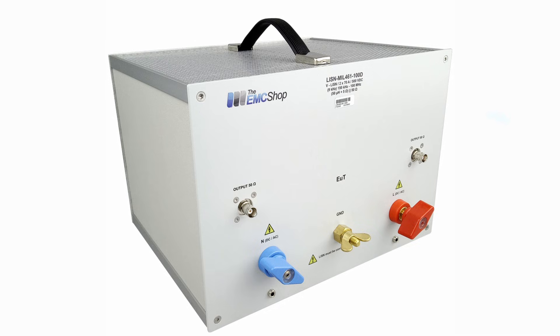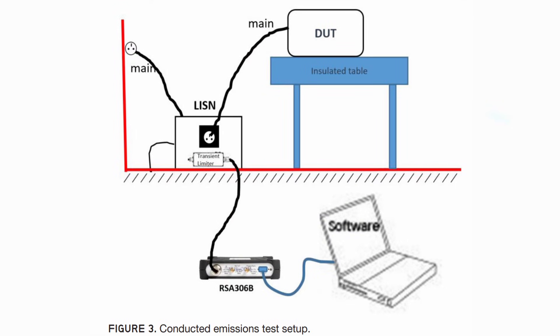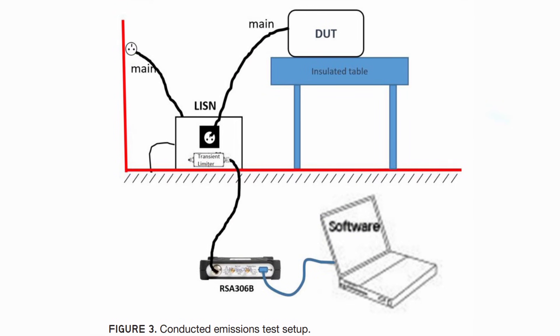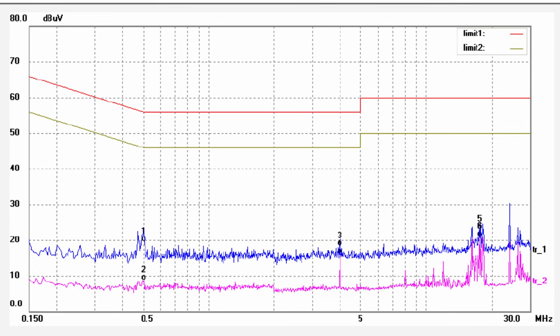With conducted emissions testing, a piece of equipment known as a line impedance stabilization network, or LISN for short, is connected between the wall outlet and the device under test. If your device doesn't ever plug into the wall, you don't have to do conducted emissions testing because there's nothing to test. For conducted emissions, the frequency range to test across is usually 150 kHz to 30 MHz, which is pretty universal across all devices. It's a good idea to become familiar with the test process for both radiated and conducted emissions, as well as the specific standards pertaining to your device, so you can better interpret the test data.